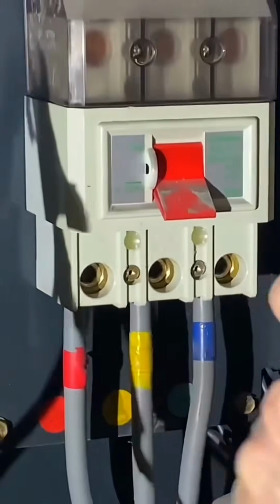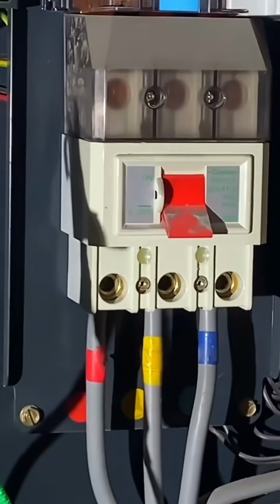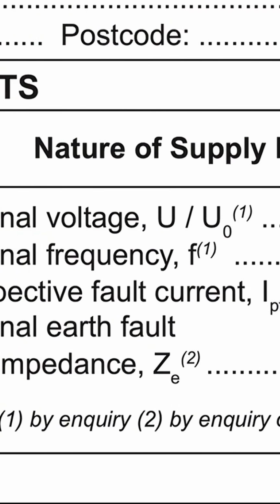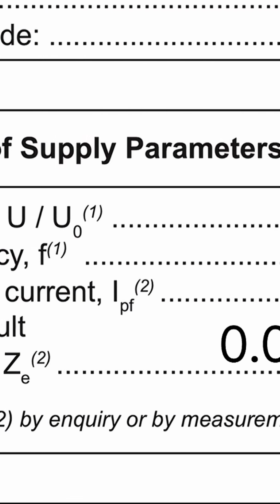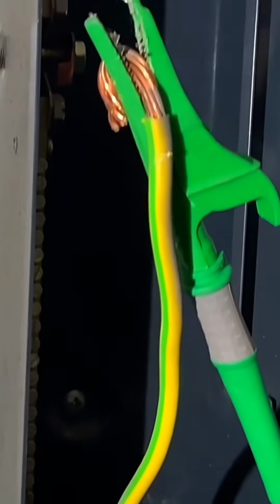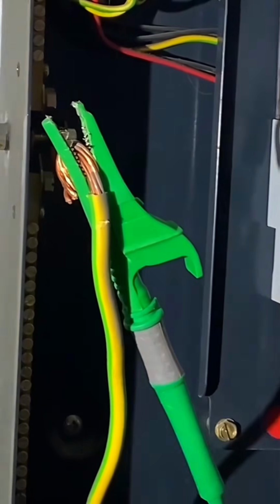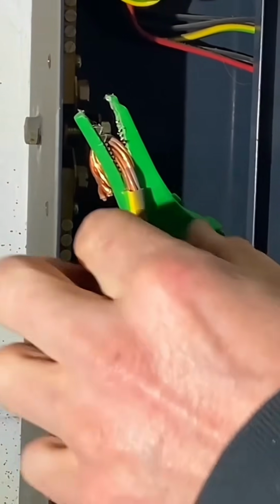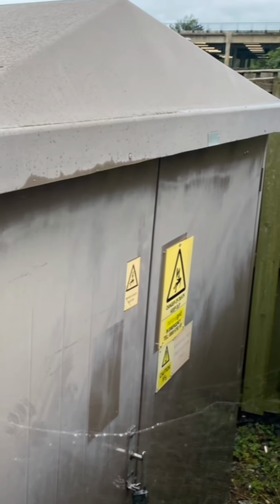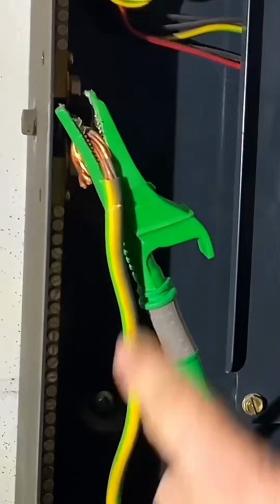So we've carried out the external earth fault loop impedance test there. We've got 3 readings. You said you're going to record the highest one in your test paperwork. Yeah. Okay, we'll remove the earthing conductor. Just remind me again why we removed that. So purely for parallel earth paths, we want the external earth fault loop impedance, and so that is the external earth that goes back to the supply transformer. Good. That is the one that has to be removed.